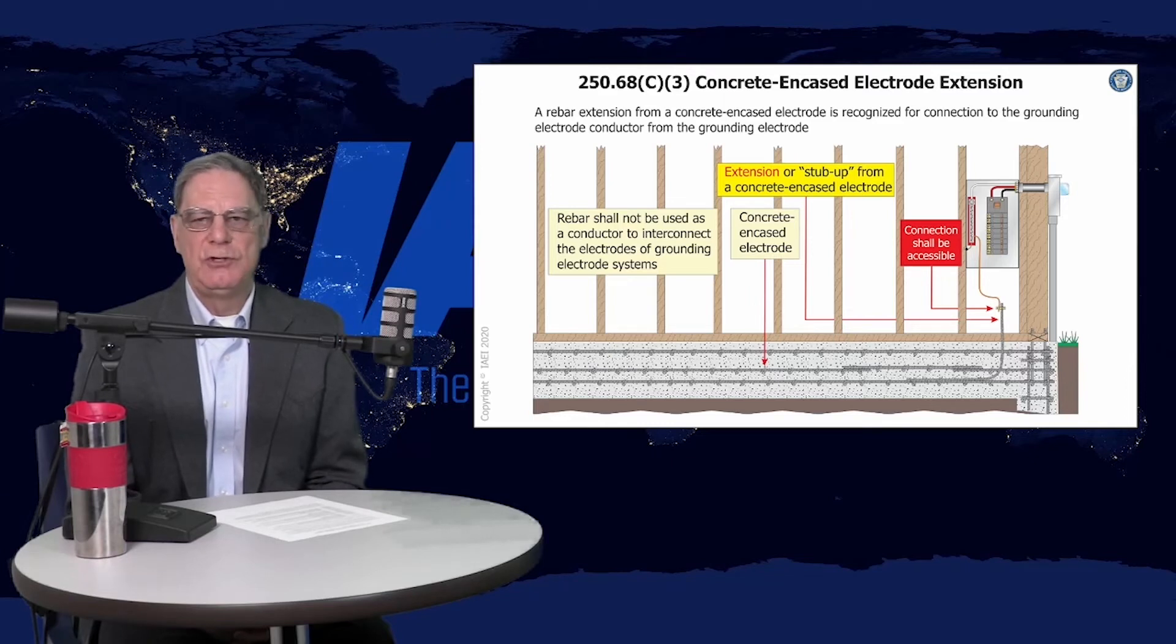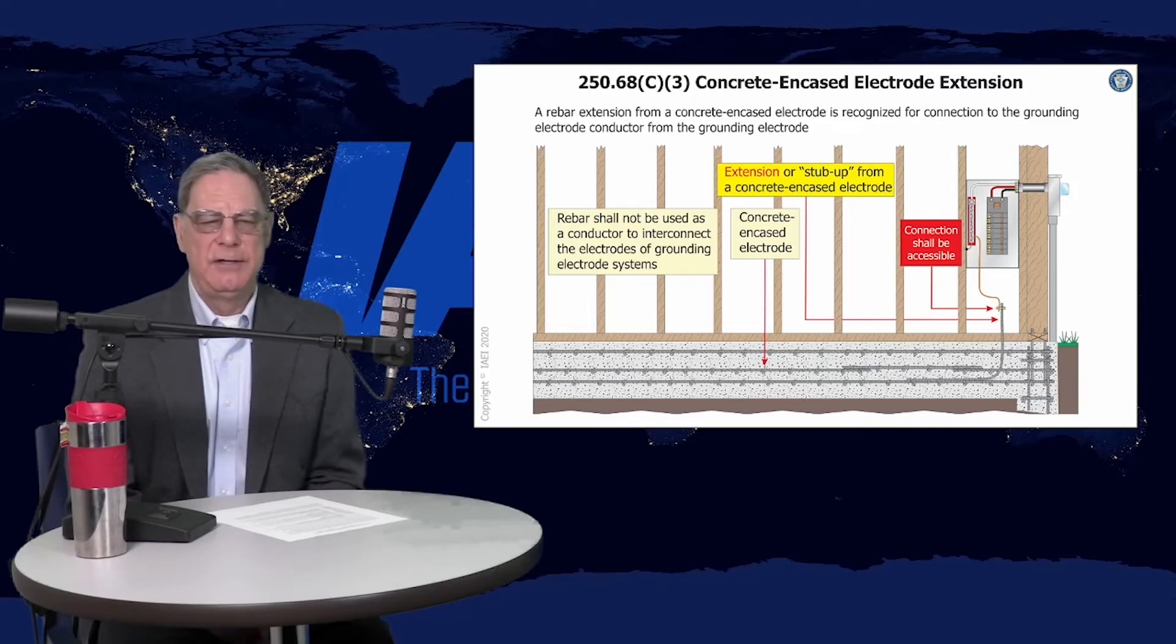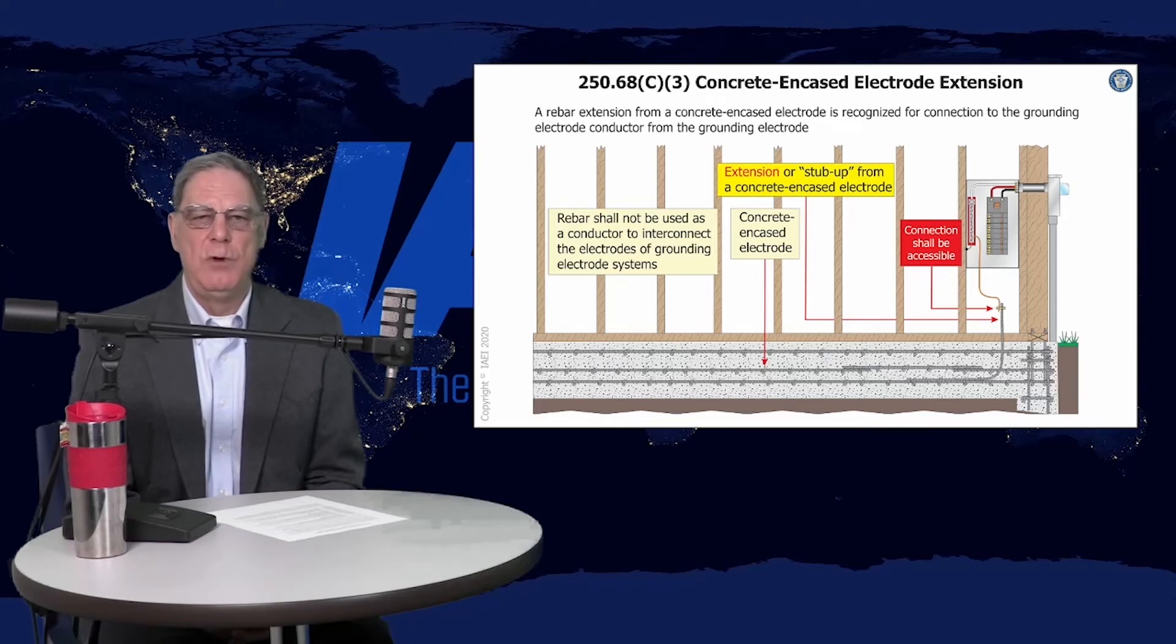One of the ways this can be made to work very easily, and it's done in many places, is to have a little piece of rebar stub up into a drywall area. This can be used to stub up, not out into the dirt out of the side of the foundation where it's going to just basically corrode away and actually cause a deterioration of the rebar in the footer, which is a structural issue.